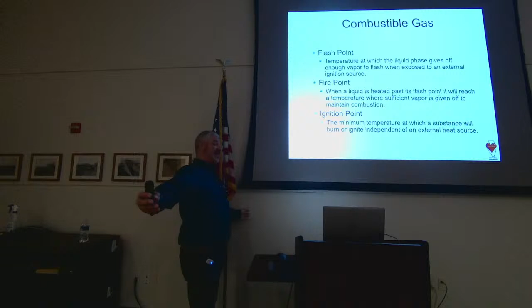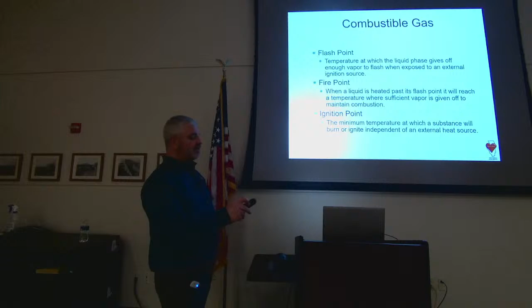Because if you get to 5% by volume, or 100% LEL, you're going to have an explosion - that happened a couple years ago, they blew the whole building out. Yep, it happens. Doesn't happen often, but it got playtime on TV. So that's LEL combustible gas.